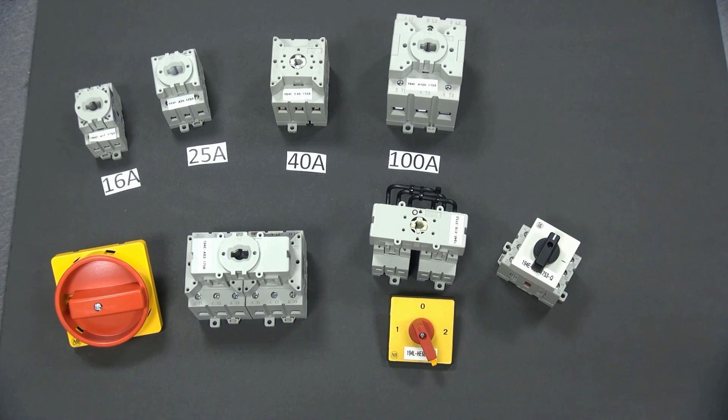Its primary function is to switch three-phase loads. It comes in the three-pole, six-pole, and change-over version with additional add-on poles, grounding, neutral, and aux contacts. Motor inductive load ratings from 16 through 100 amps.